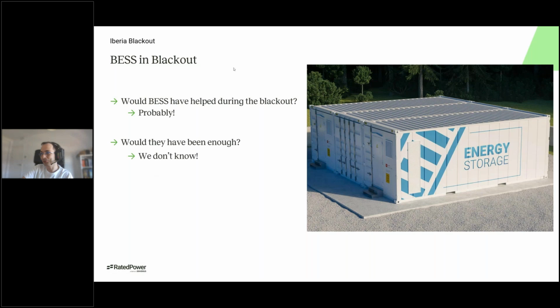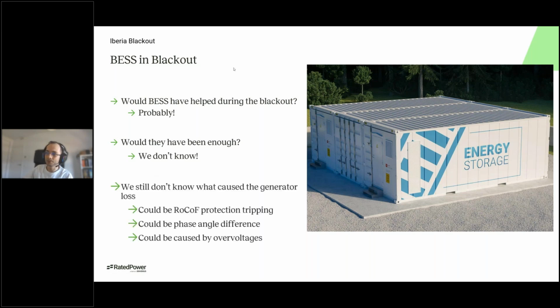Well, that's an unknown. We don't know. Maybe even by placing gigawatts of active power from the batteries, it wouldn't have been enough, because the last question is that we don't know what caused the generator loss. We're assuming that it was the frequency drop that made other generators just disconnect. It could be a rate of change of frequency protection tripping. It could be due to a phase angle difference with Europe, for example. It could be caused by over voltages. There are some people reporting over voltages a few seconds before the blackout. So we don't really know the cause, and without knowing the cause, it's very bold to assume that battery systems would have been able to prevent this issue. So until we know what really happened, everything is just opinions. So yeah, we will see about this.